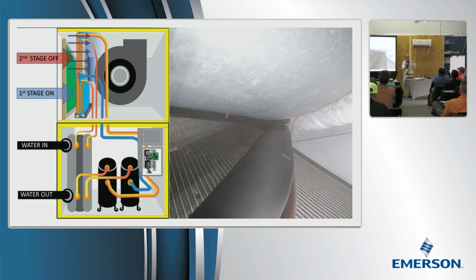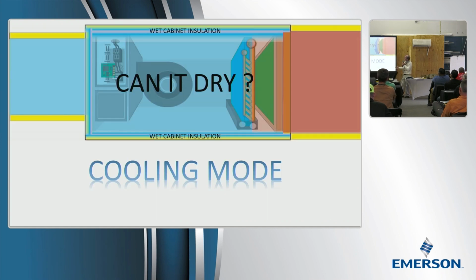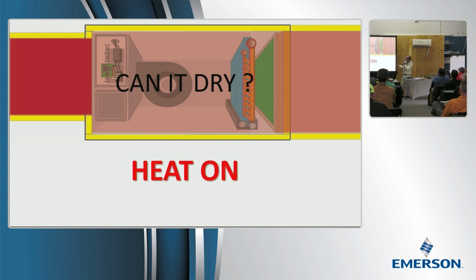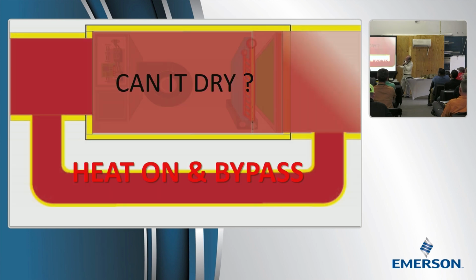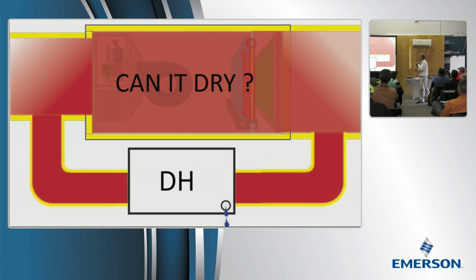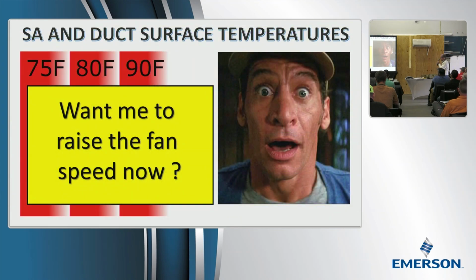And that's why you want an interlace coil. This is a number one. In my climate, if you have an over-under coil, you can't let that much moisture around. So we basically couldn't do it. If you want to dry it out, you can turn the heat on, you can run the fan, you can bypass it. It will not dry out on its own during cooling season. There's a little trick: get a dehumidifier. If you don't want to heat up the inside of the house, but you want to dry it out, you could do that. But you've got to get it dry before you can move forward.